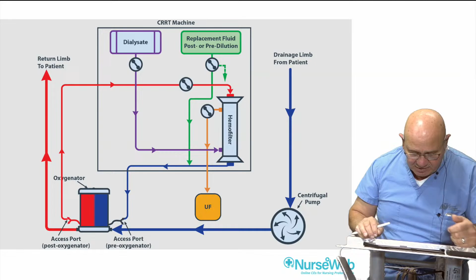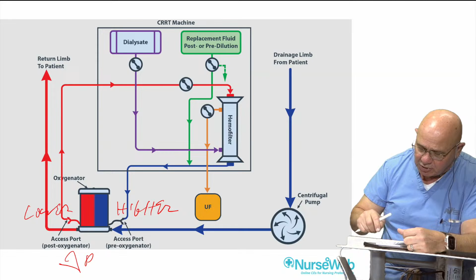Here's another way to do it. In this particular case, we're using the oxygenator access port coming up, going through the filter, and returning it to the access port on the oxygenator. Again, you can try to do it this way, but I don't recommend it. These are, again, ways that it can be done that have been published. The problem with this is, remember, this oxygenator has resistance through it. So your pressure on this side is going to be higher than your pressure on this side, because you have the resistance through the oxygenator plus going to the patient, whereas here you only have the resistance going to the patient. And of course, remember, this is your delta P, or your difference in your pre-oxygenator versus post-oxygenator pressure. Very challenging to do it this way.